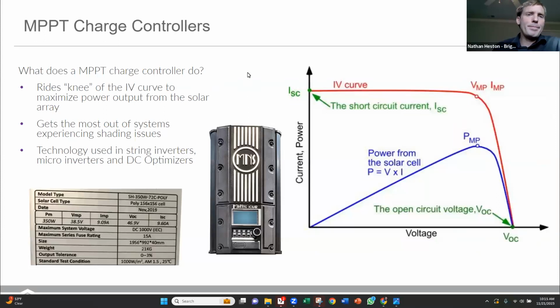I'm showing an MPPT charge controller here. This is a MidNite Solar charge controller. And again, what the MPPT is designed to do is increase the current, right, which causes the output voltage of the panel to drop, or the array to drop if you're doing multiple panels. And by increasing and decreasing that current, changing that voltage, we're able to track the maximum power point of the panel.